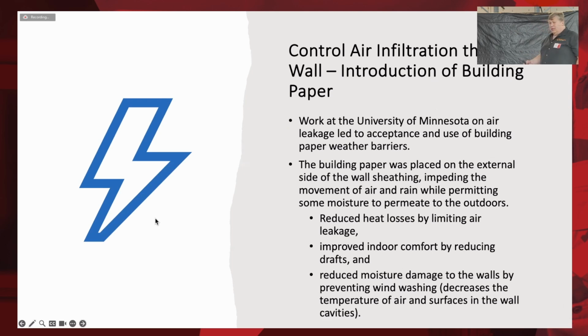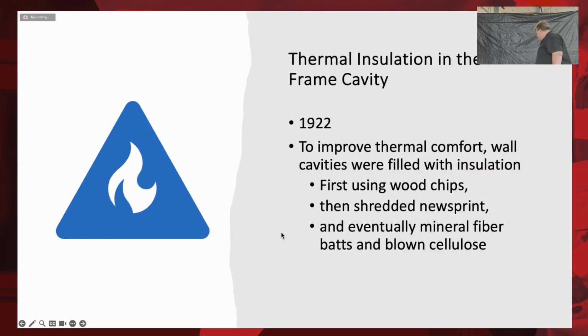Our building code has always recognized the need, from the very first day we had one here in Canada, to control vapor diffusion when you have an insulated assembly separating an environment. You must be concerned about the volume of air, for the purpose of controlling that convective resultant deposit of water, air flowing through and more moisture-laden air finding cold surfaces in there.